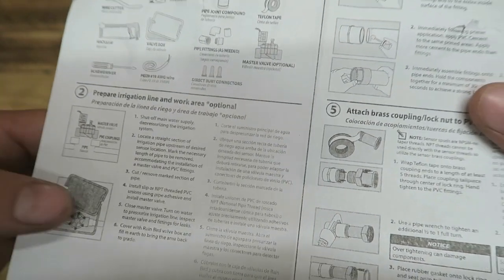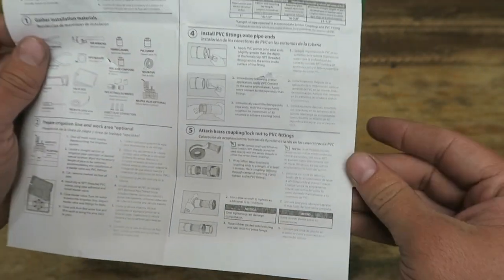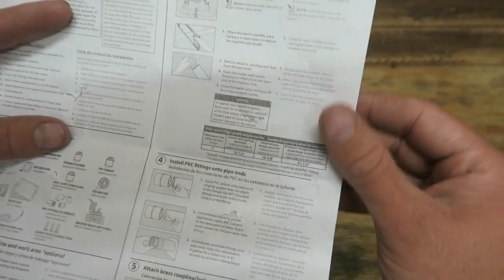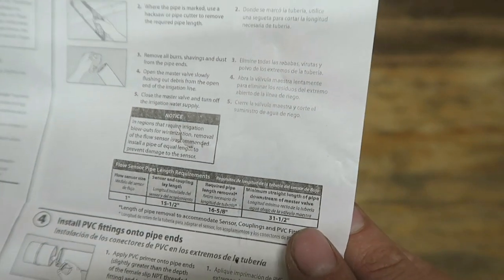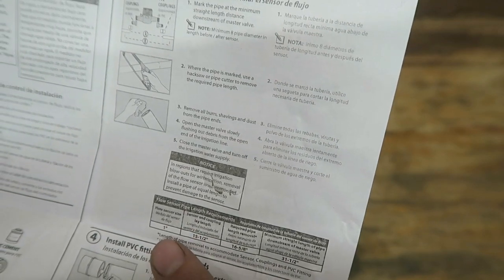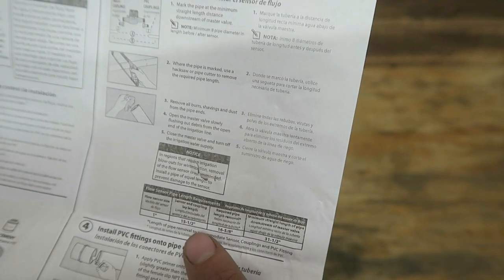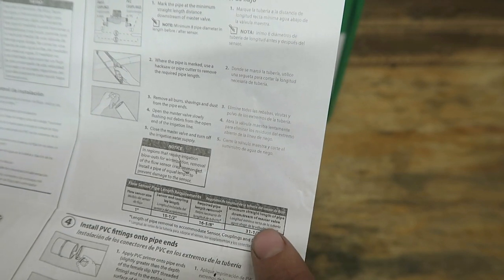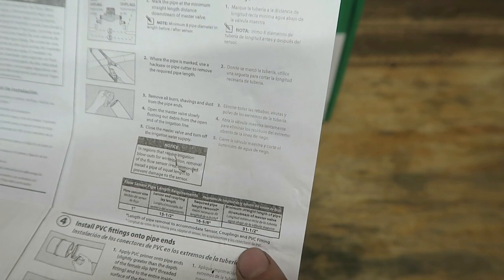A lot of times with a flow sensor, they'll require a certain amount of feet to be undisturbed in front of it. They don't want a 90-degree fitting right in front of it because that will disturb the flow. The flow sensor size is a one-inch flow sensor. Sensor and coupling length is 15 and a half inches. Required pipe length to remove is 16 and five-eighths inches. Minimum straight length of pipe downstream of master valve is 31 and a half inches. Make sure you've got plenty of straight section — you don't want to put this in a tight space.